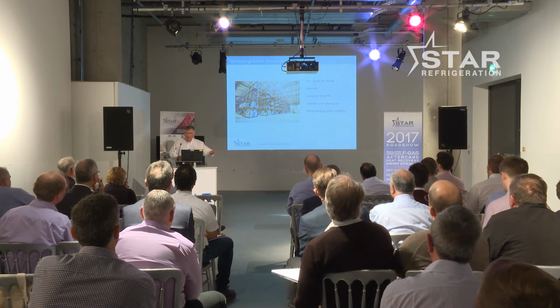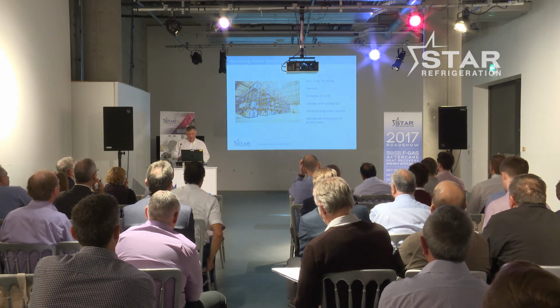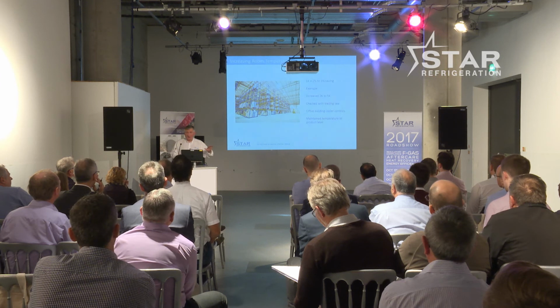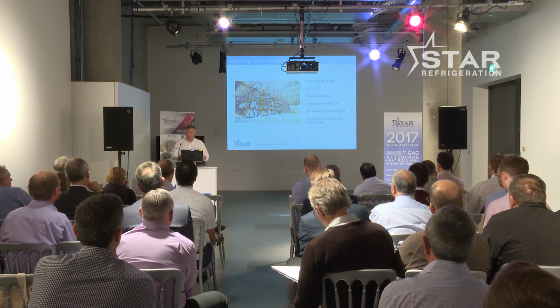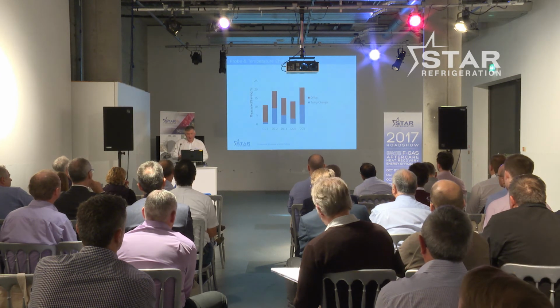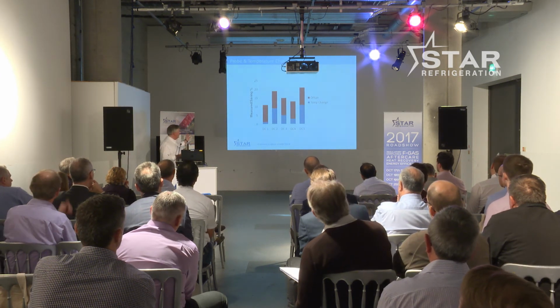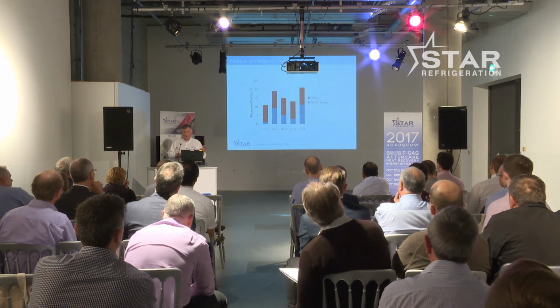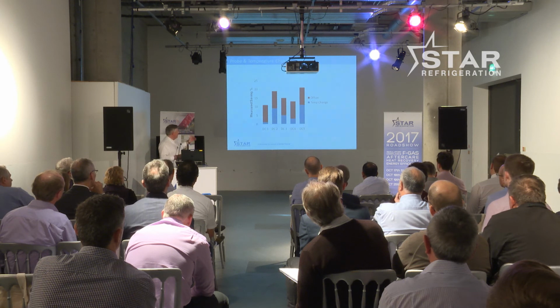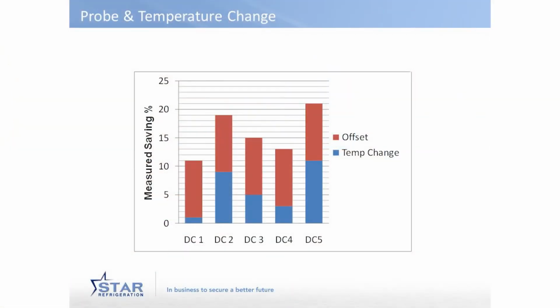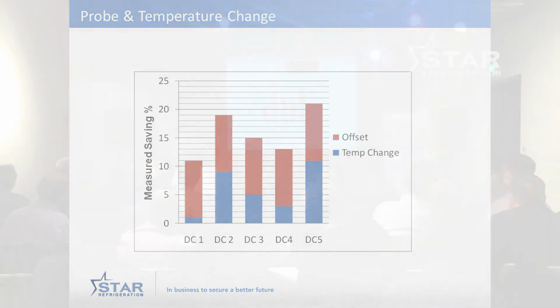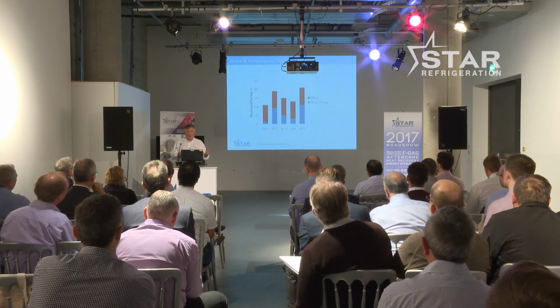We then did that by just putting an offset on the existing controls and maintained the temperature at the product level at the same level as it had been before, but by running the plant more efficiently by raising the suction temperature by 2 degrees. We did this across 5 of their warehouses, and half of the benefit in each case was achieved through offsetting the temperature, and the other half was effectively achieved by measuring the temperature at ground level instead of ceiling level. So there was up to 20% saving in energy within this distribution centre by just making these simple changes, moving a sensor which didn't cost a great deal and changing a set point which cost even less.